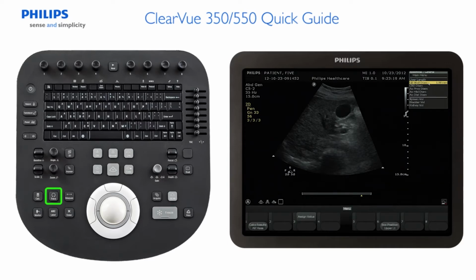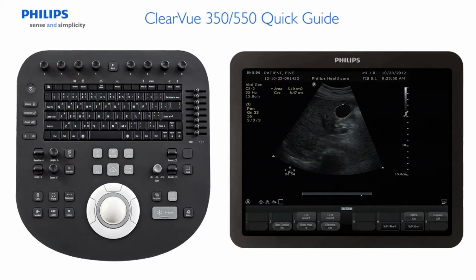The Trace key displays a caliper to perform the trace function in any mode. The active trace will be displayed in amber. To begin a measurement, press the Trace button, then press the left trackball button. While performing the trace function, you can back up on the trace line to erase that portion of the trace line. To complete the trace, press the middle trackball button. Please note that the type of trace, ellipse, or manual can be selected in the setups.